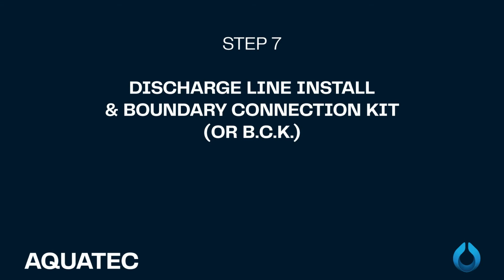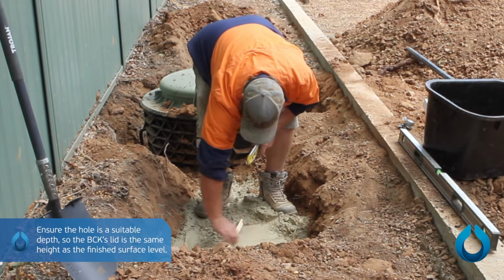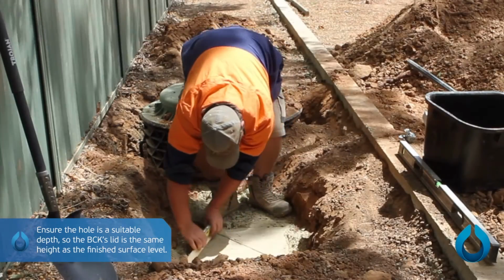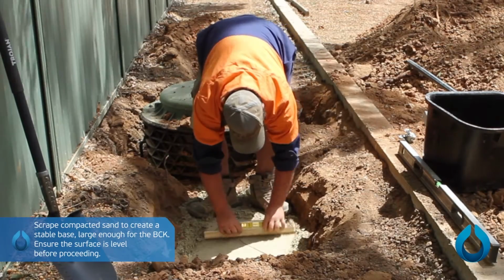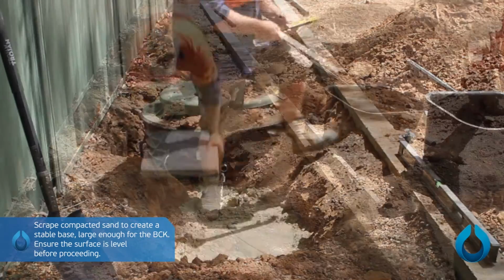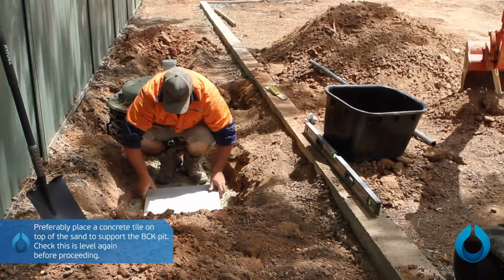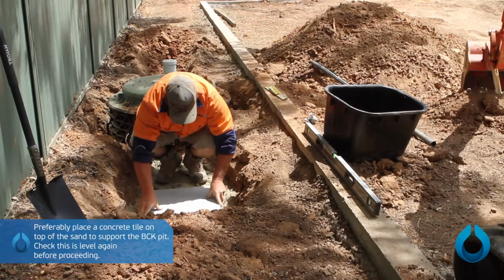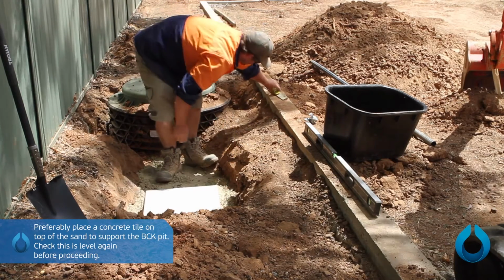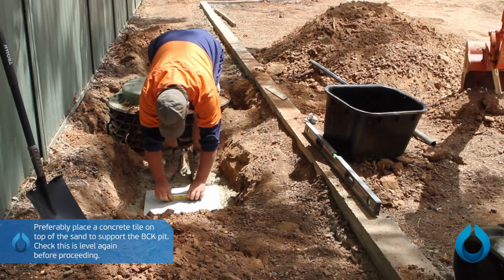Step 7. Installing the discharge line and boundary connection kit, or BCK for short. Ensure the hole is a suitable depth, so the BCK lid is the same height as the finished surface level. Scrape compacted sand to create a stable base. Place a concrete tile on top of the sand to support the BCK pit. Check this level again before proceeding.